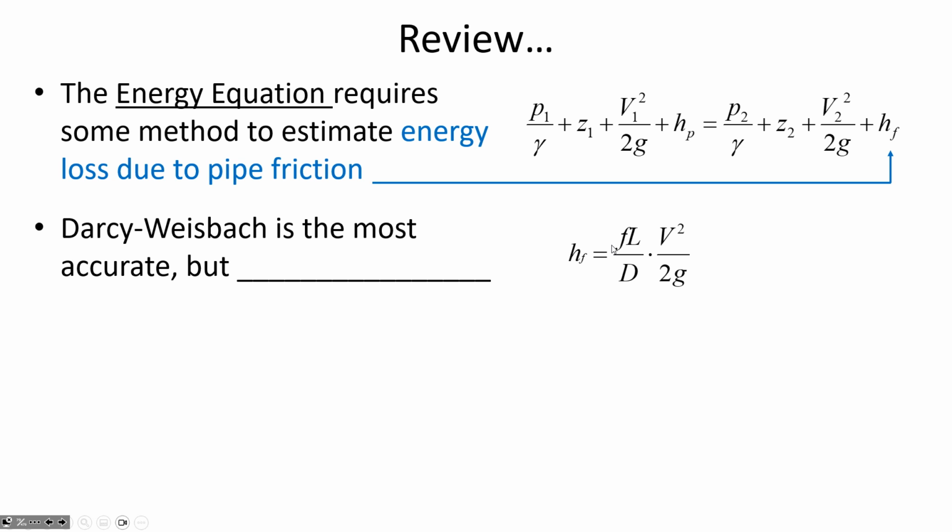Sometimes the problem statement won't give you the velocity directly, and even still, it's trickier to estimate F than it would be for some of the other methods. But that's just a review of why we like the Darcy-Weisbach equation, because of its precision. And you know what we're saying is a problem with the F value? Actually, that's not a problem at all. That's not a bug, so to speak. That's a feature.